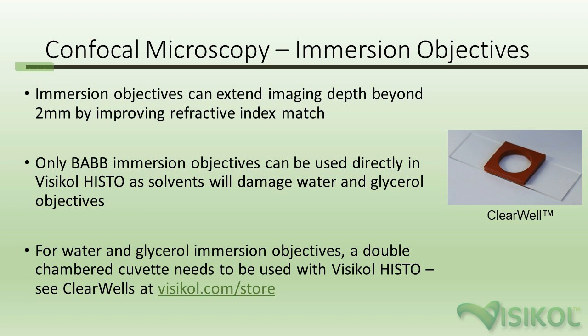For immersion objectives, if you want more depth, you can use a dipping objective matched to water — which is not ideal for VisiCol Histo — or a BABB immersion objective, which is solvent-compatible and can go directly into VisiCol Histo. We suggest that water dipping objectives are not placed directly into VisiCol Histo; instead, use these water and glycerol immersion objectives with a double-chambered cuvette, where the inside contains VisiCol Histo M and the objective does not contact it. These are available on our website at visicol.com/store and are called ClearWells.